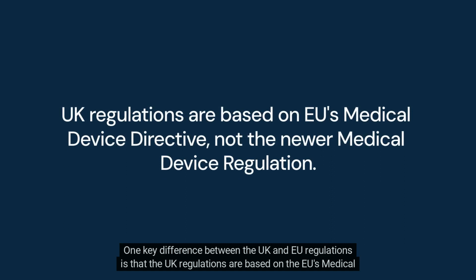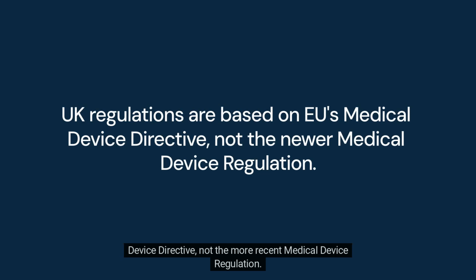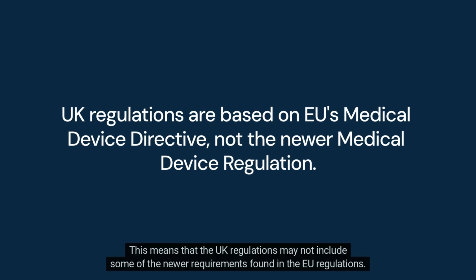One key difference between the UK and EU regulations is that the UK regulations are based on the EU Medical Device Directive, not the more recent Medical Device Regulation. This means that the UK regulations may not include some of the newer requirements found in the EU regulations.